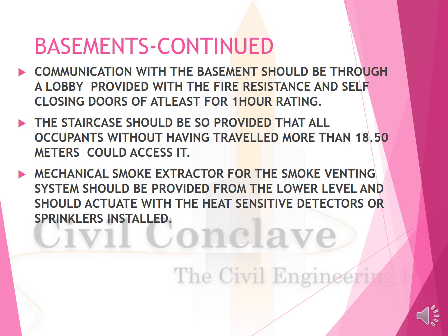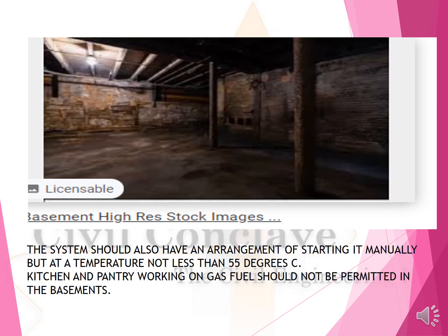Mechanical smoke extractor for the smoke venting system should be provided from the lower level and should actuate with the heat sensitive detectors of the sprinkler installed in the basement. The system should also have an arrangement of starting it manually, but at a temperature not less than 55 degrees centigrade. Kitchen and pantry should not be permitted in the basement.